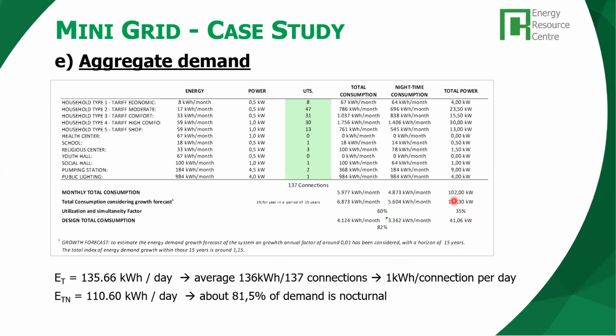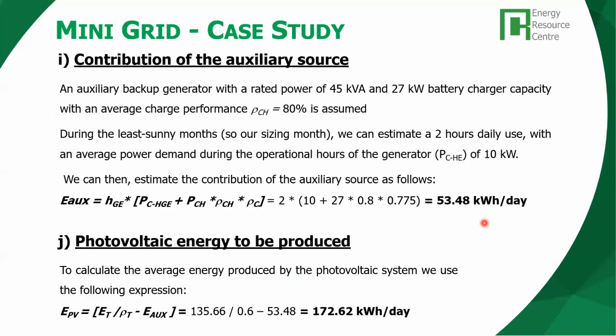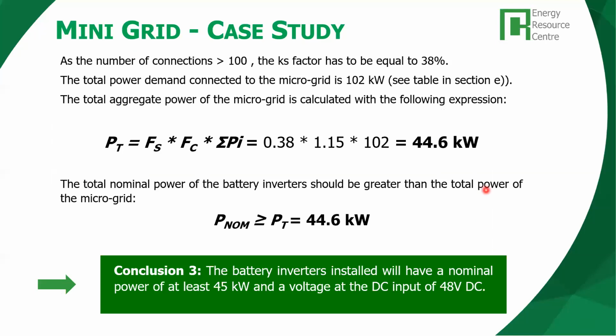We have 102 together with the growth factor, 117. Then we apply the simultaneity factor of 35%. We bring it down to 41 kilowatt net power demand for this community. That would be the peak. We expect it to be in the evening. So if we consider a simultaneity factor of 38% instead of 35, we get the nominal peak power demand around 44.6, let's say 45 kilowatt.